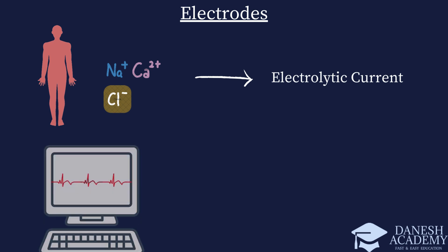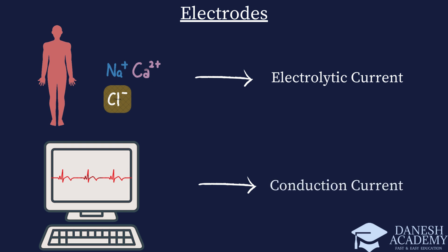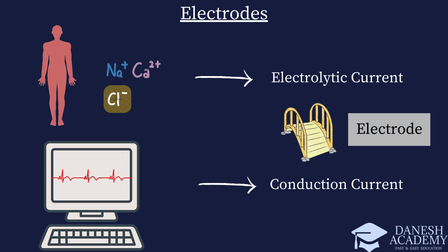Electrical conduction in the human body occurs through the movement of ions, meaning that the electrical currents in the human body are electrolytic currents. This is in contrast to the conduction currents used in electronic devices. To bridge the gap between the electrolytic currents in the body and the conduction currents in electronic devices, we need a converter — and electrodes are the answer. Electrodes serve as the interface, facilitating the conversion of one type of current to the other, enabling effective measurement and display of biosignals.